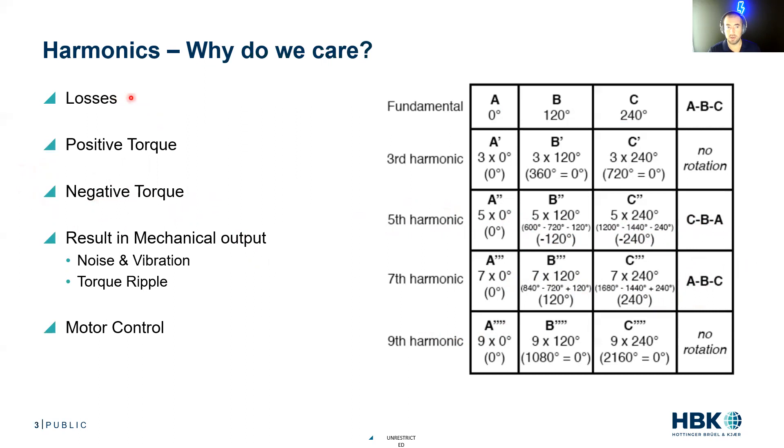So why do we care? Because these harmonics have their own individual losses. They can cause positive or negative torque, but maybe not where we want it. They do result in mechanical output, so we could have noise and vibration. Anytime you're causing torque, you're causing radial forces.